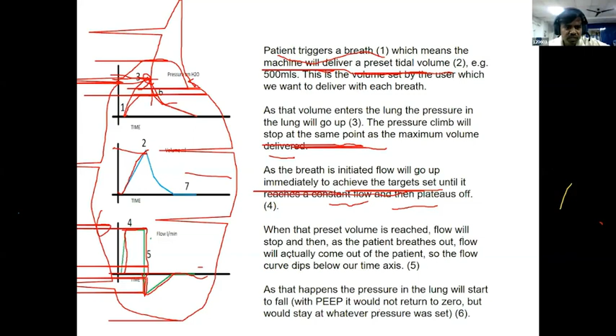So you have to observe here. If you see one by one, this is volume control. You see pressure versus time, flow versus time. Time is triggered from the ventilator, and the pressure and flow from the patient, right? Volume versus time. You see here the pressure curve, normal curve: inspiration, plateau pressure, and then expiration. And then it's not coming to zero, because we are keeping PEEP 5. So in the pressure curve, it won't come to the zero level.